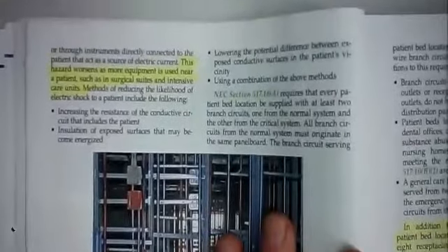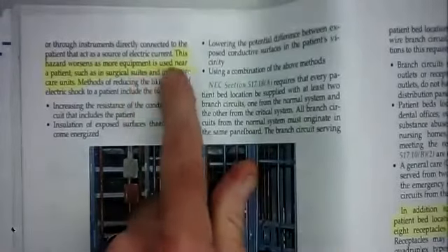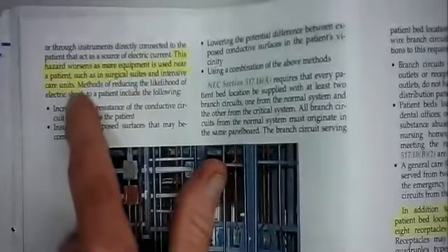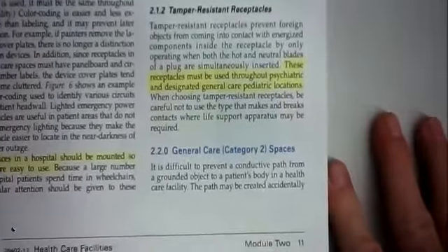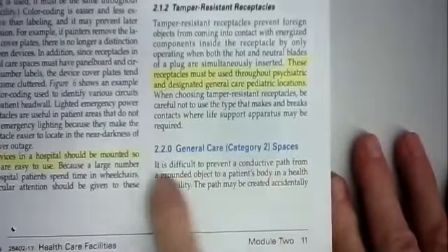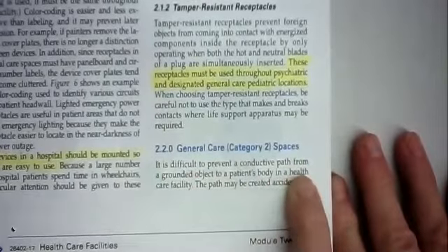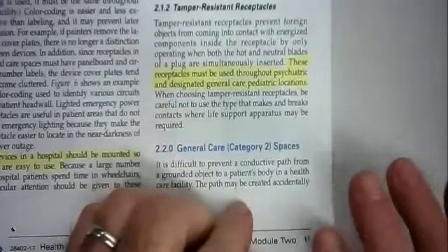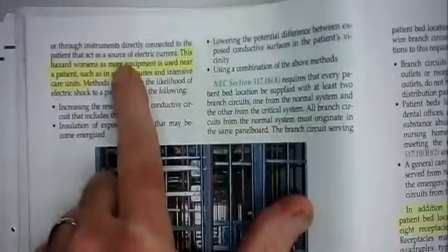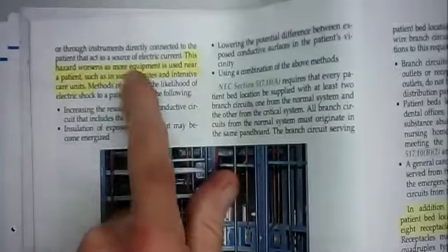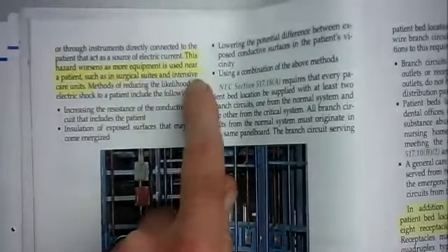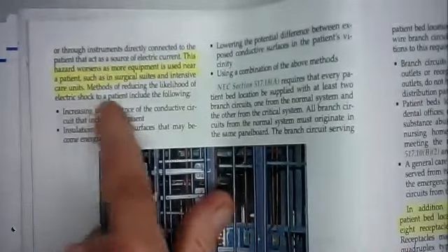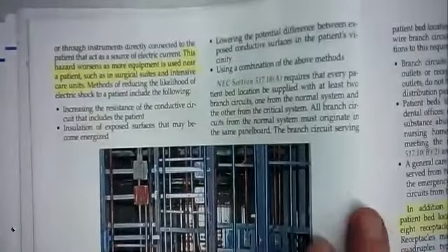At the top left-hand side of page 12 it says, this hazard worsens as more equipment is used near a patient, such as in surgical suites and intensive care units. Well, let's go back and read a little bit because we want to know what it is that they're talking about. Over here on page 11 on the bottom, it says general care spaces. It's difficult to prevent a conductive path from a grounded object to a patient's body in a healthcare facility. The path may be created accidentally or through instruments directly connected to the patient that are a source of electrical equipment or current. This hazard worsens as more equipment is used near a patient, such as in surgical suites and intensive care units. Methods of reducing the likelihood of electric shock to a patient include the following, and then they give us some bulleted points. We have to make sure that we have that equipotential plane, everything on the same potential.